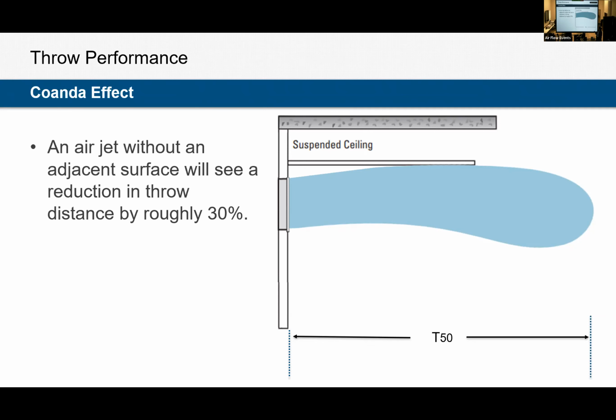If we don't have Coanda, we will see the throw distance reduce by about 30%. So if you have a black, let's assume that speaker right there is a diffuser and it was releasing into this space without a ceiling. It will throw out horizontally, but it has nothing to stick to. So it's going to start dropping into the space much faster. That means our throw distance will be 30% less than what the catalog is showing because we don't have a ceiling. The same thing would be true here with a sidewall grill. If our sidewall grill is so low that it's not going to catch onto the ceiling, the throw distance will be shorter than what is cataloged.